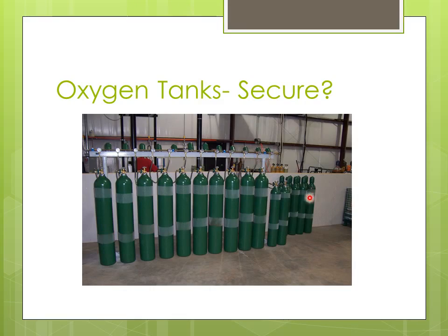In fact, over here you see similar. You can see them kind of here. They're kind of like bowling pins, but there's nothing holding them. So this would be a clear issue, having these cylinders just standing on their own like that, and it could be quite dangerous. I would hate to think what would happen if one of these cylinders were to fall over and crack its valve. It could almost be catastrophic, to be honest with you.